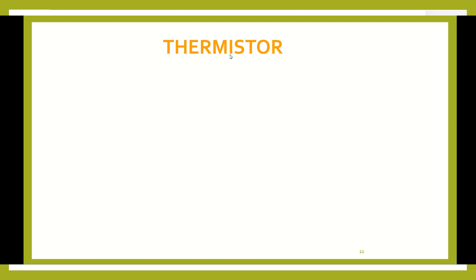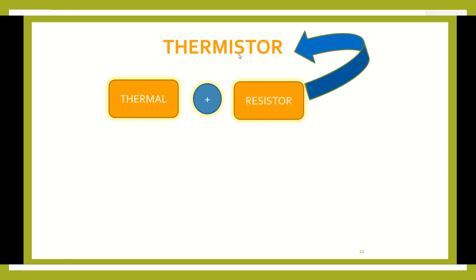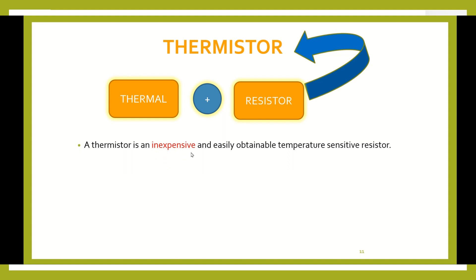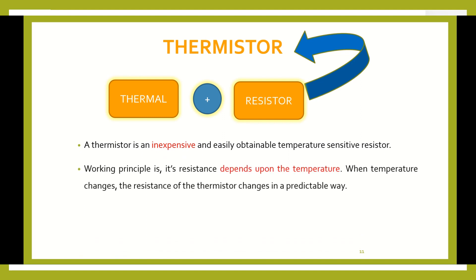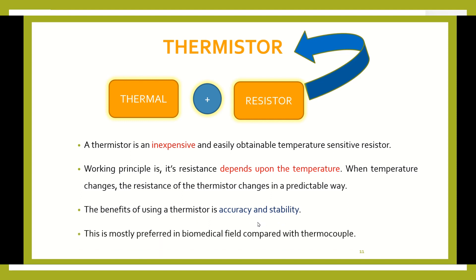The third device used to measure systematic body temperature is the thermistor — a combination of 'thermal' and 'resistor'. Due to the body temperature, the resistance changes, which is why it is called a thermistor. It is a very cheap device, mainly useful in the biomedical field. The resistance varies depending on temperature. The benefit of the thermistor is that it gives good accuracy and stability, so it is mostly used in the biomedical field.